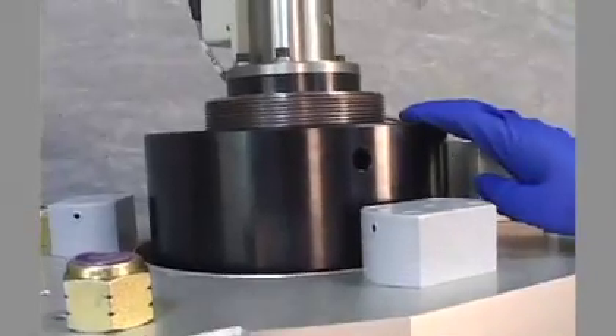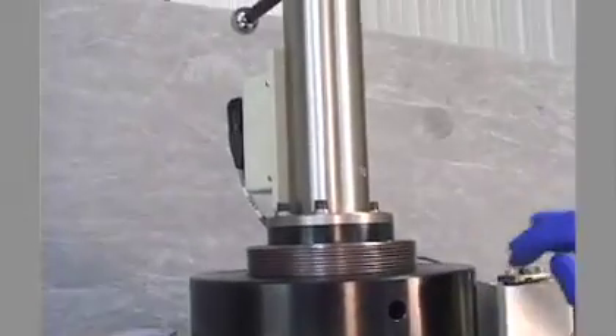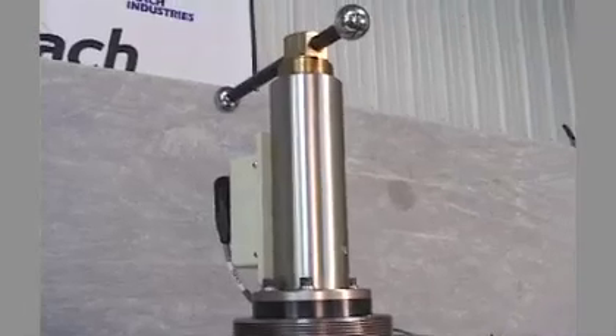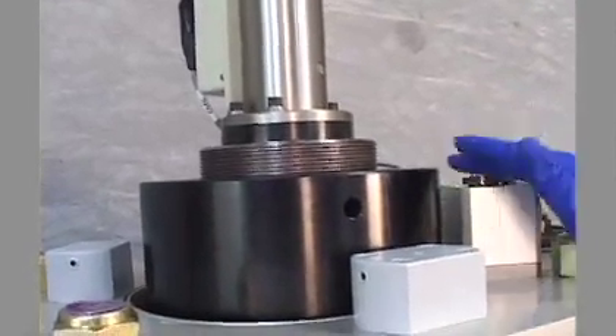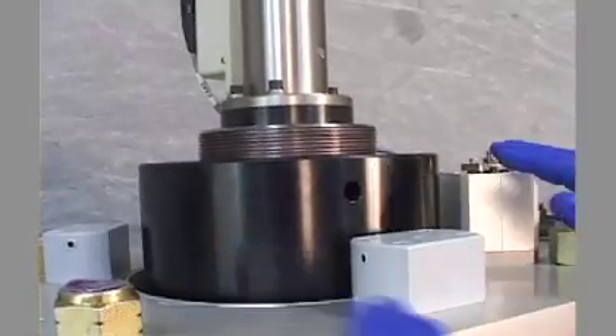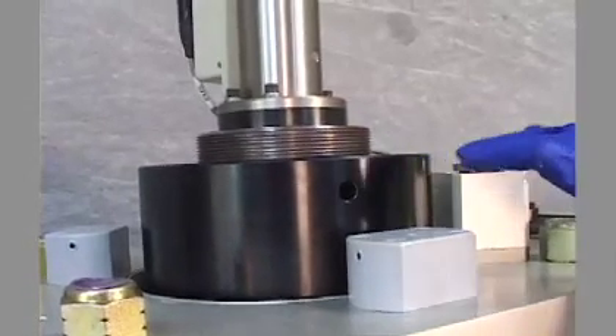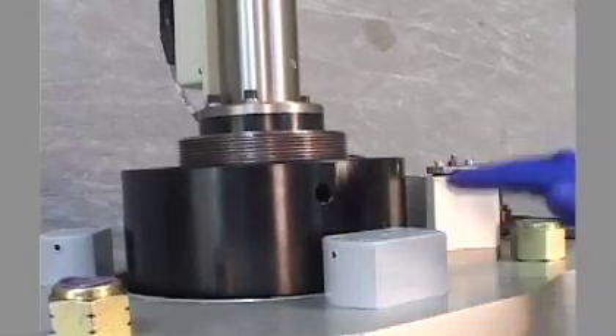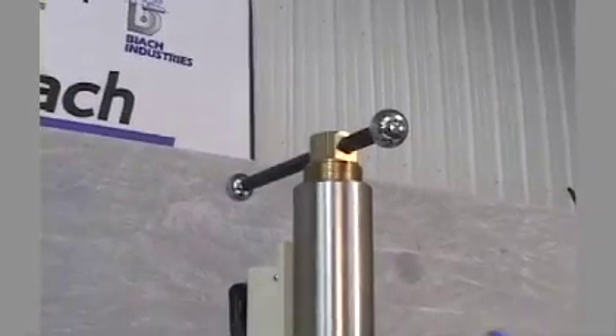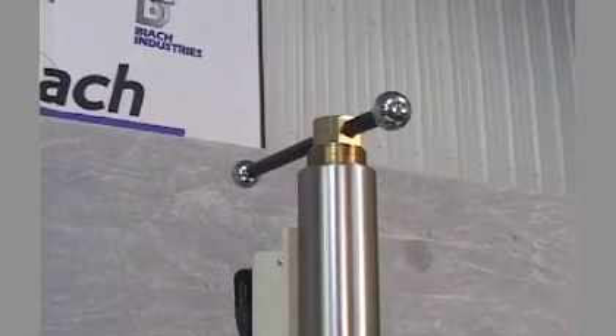This big cylindrical nut is called a holding nut. This is basically what holds back all that hydraulic pressure on the pull system. When you're pulling, this is what's holding it in place. And this is also adjustable. It's on a big thread on the puller bar itself, and this is adjustable for the height of the studs that you'll be on. This handle up here is a fine adjustment for latching and unlatching.